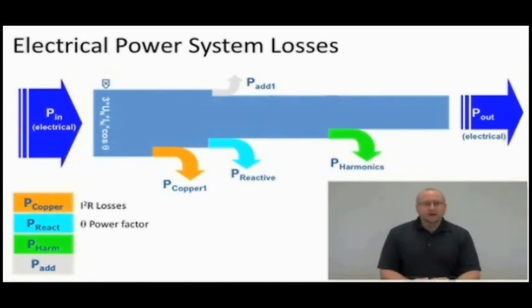And that's the amount of heat that's created when current flows through a wire. If current flows through a wire, it heats up. That heat is lost energy that could have been used for something else. So one way you can minimize your copper losses is by selecting the proper cable size. If your cable is too small, it increases the resistance, and that's going to increase your copper losses. So that's one way that you can minimize your copper losses and your electrical power system losses, by selecting the proper size of wire, the proper gauge wire.